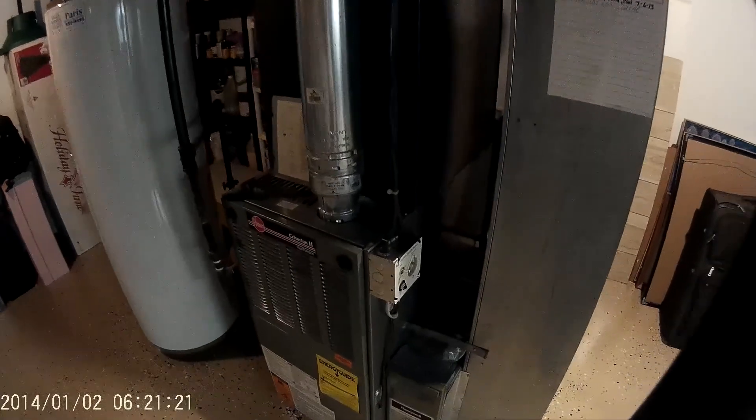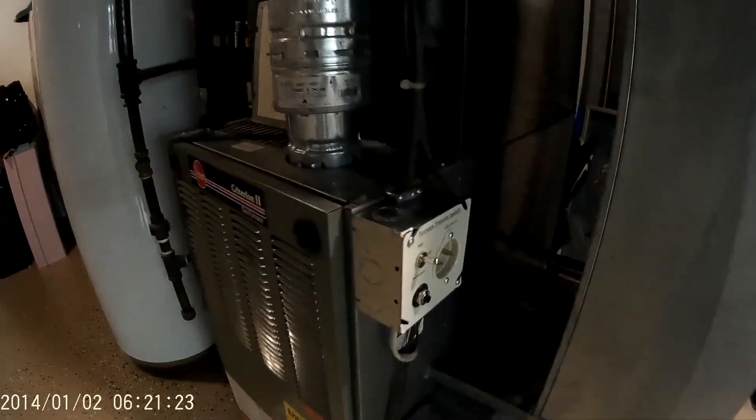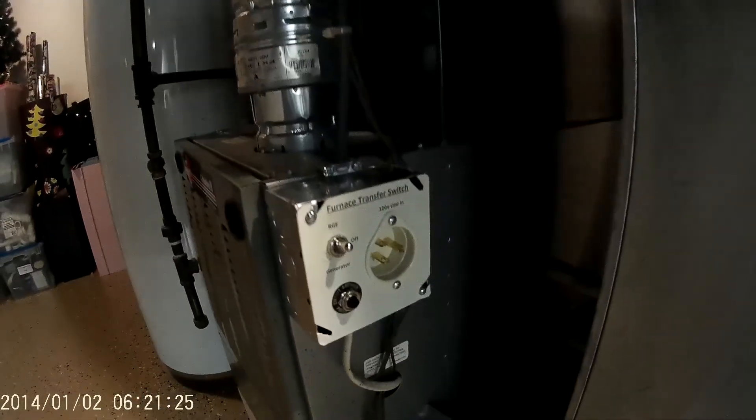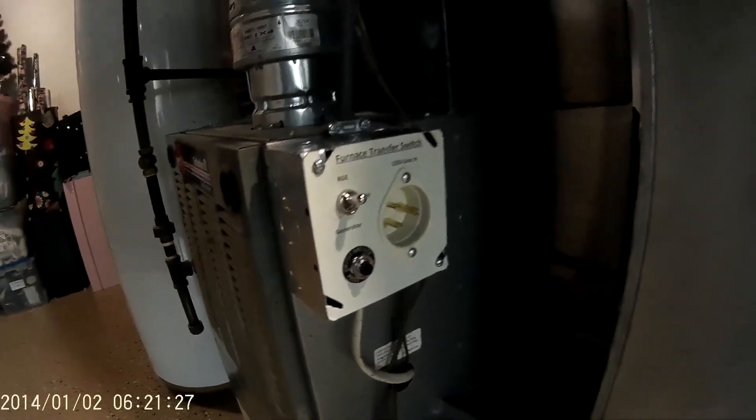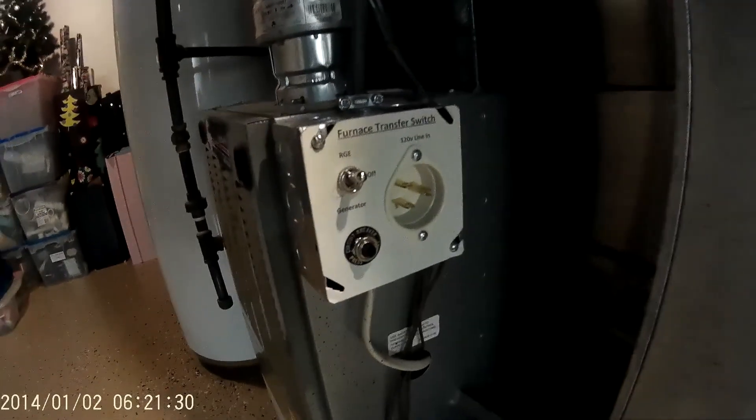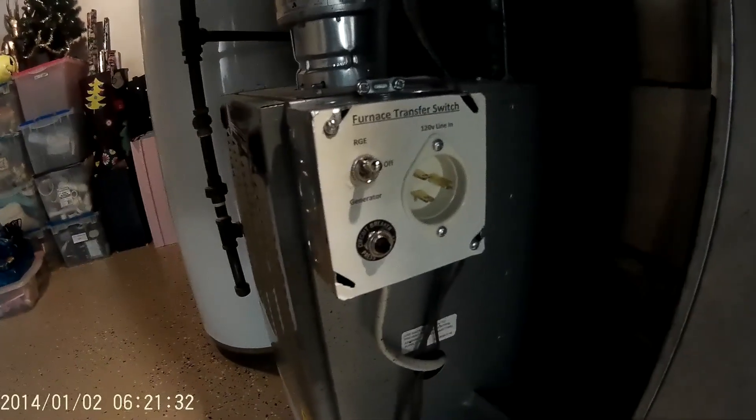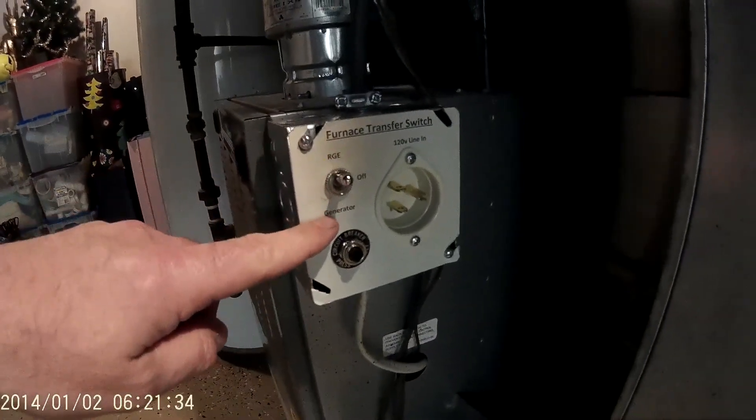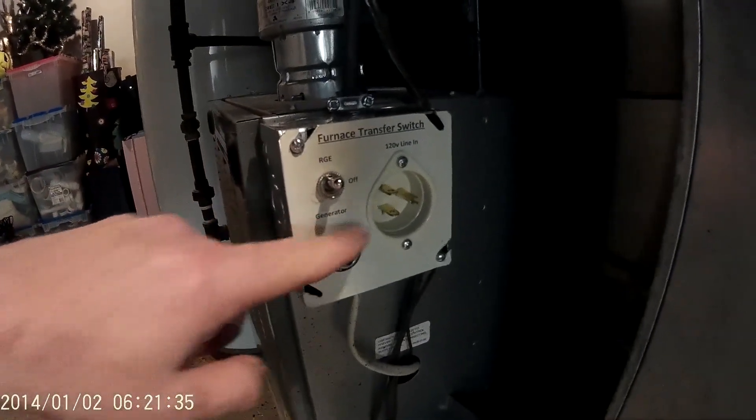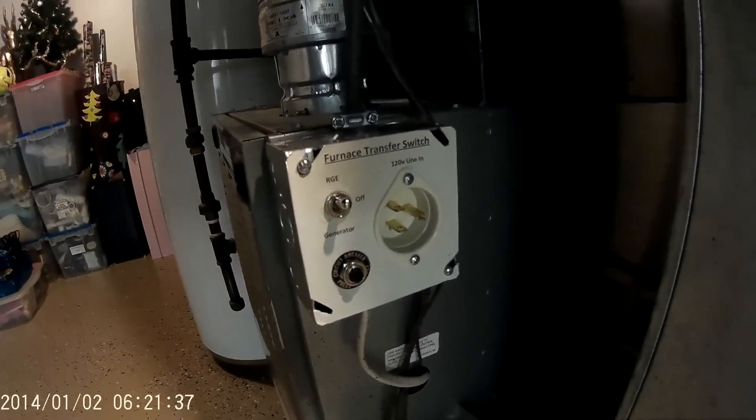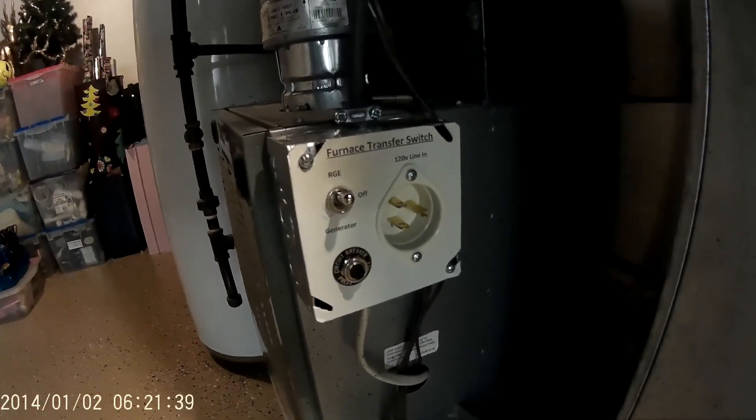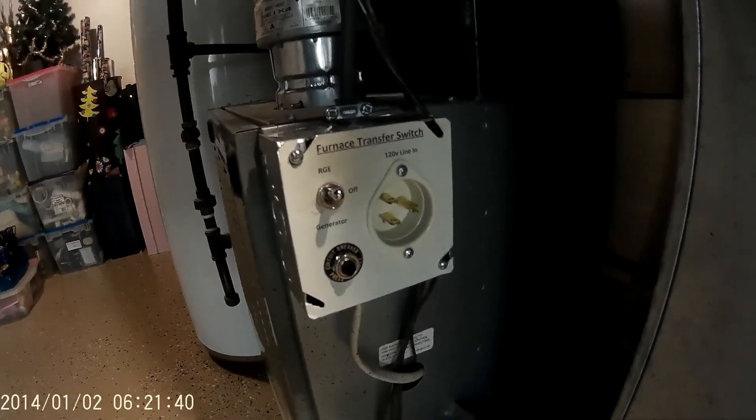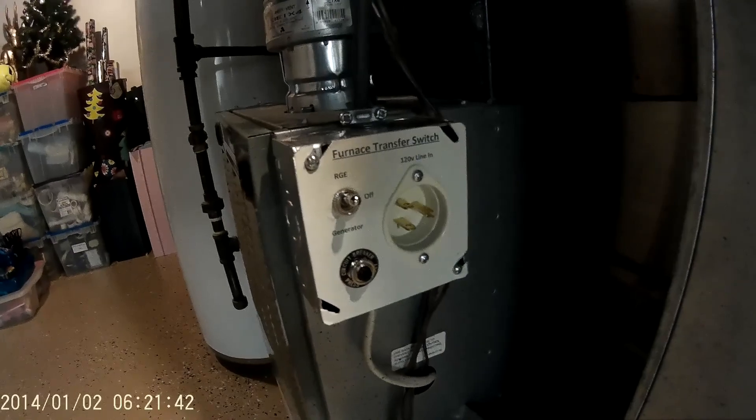Okay, so here's my furnace, and I just took the switch that was on the furnace off and replaced it with my transfer switch box and tested it with line power and also flipped it over to generator and plugged in a cord just from another household outlet on a different circuit and confirmed the switch acts exactly as it should.